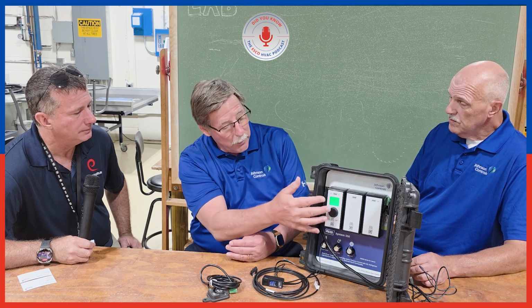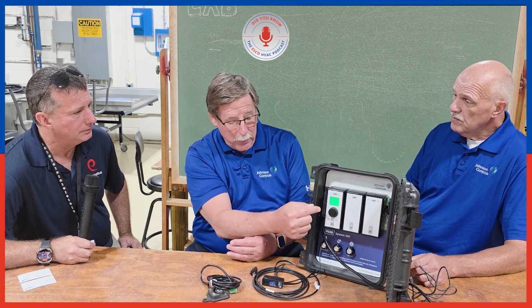Okay. Because we can see the LFL level. Yeah. In addition to the features that I talked about, there's also a 0 to 10 volt output that you can, again, tie into a supervisory controller, and it will tell you the highest LFL value of any sensor connected to the controller. Okay. So in this case, we know, because we saw the 25% LFL, but specifically, as Bill talked about earlier, you have the ability to name your sensors, so you can actually tell, okay, it was the number one sensor that's located on the left-hand side of the evaporator coil, and I know that's the one that I need to pay attention to on the leak side.